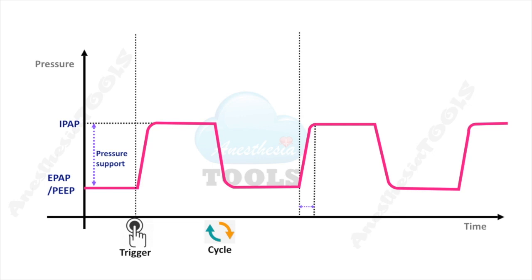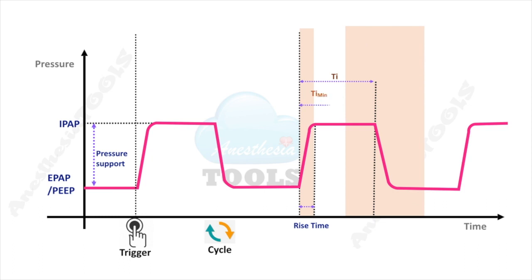If rise time is short, the flow must be high to reach IPAP quickly. If rise time is longer, a lower flow can gradually build up pressure to IPAP. The time until cycling to exhalation is the inspiratory time TI. The patient may cycle over a range: TI minimum is the minimum allowed — even if the patient tries to exhale earlier, the machine delays cycling. TI maximum is the upper limit — if the patient hasn't cycled by TI max, the machine forces cycling to exhalation.